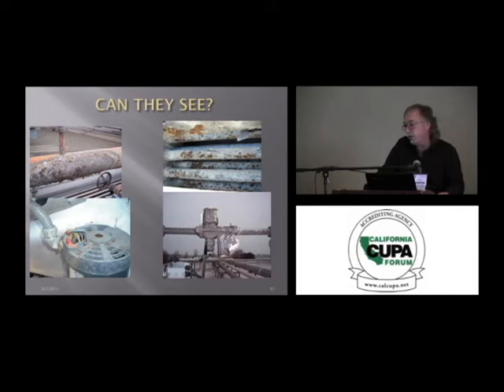And so what happens is at startup, the zinc comes out of the galvanizing and then reattaches itself. It's looking for carbon steel. And it will quickly eat through the galvanizing. Then they have no protective coating for their tubes anymore in their condensers. And those are only 40 thousandths thick approximately from the factory. So it is a weak point for us.